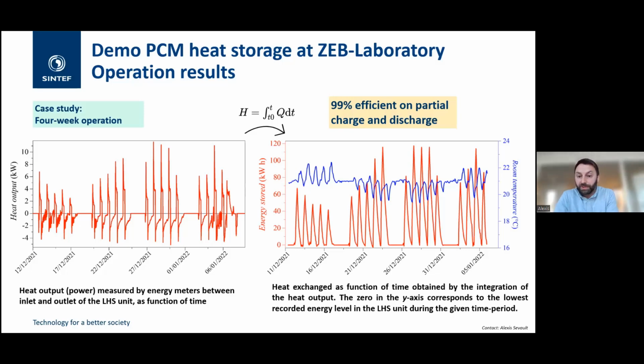We also measured how much heat goes in and how much goes out, and then we averaged it over several days. We figured out that we're actually at less than 1% heat loss on average, which means it's 99% efficient, including in partial charge and discharge. That means 99% of what goes in goes out, and the rest is heat loss. In that case, the heat loss is in the room, which is in the middle of the building at the ground floor, so it's not an actual loss, but for the sake of system evaluation, it is a loss. Anyway, very satisfying to see it's 99% efficient in that case, which is way above what you could think of with batteries and some other systems.